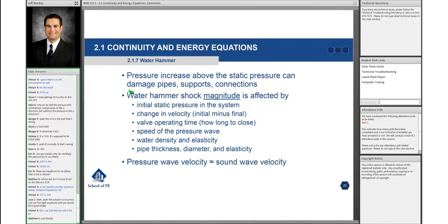The magnitude of that water hammer shock is affected by: the initial static pressure in the system, the change in velocity - if we have really high velocities and then suddenly close the valve - valve operating time, how long it takes to close instantaneous versus slow, speed of the pressure wave, water density, elasticity, and the pipe thickness, diameter, and elasticity.